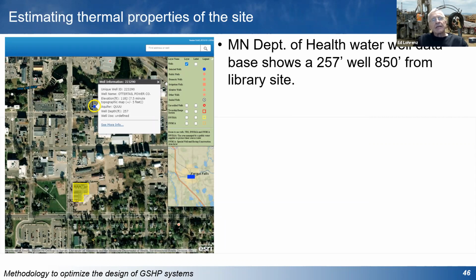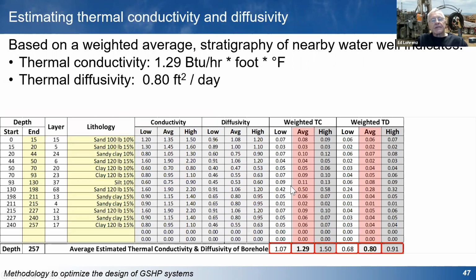First of all, in addition to the energy loads that we're trying to deal with, we've got to try and figure out what the geology is, what that can handle. Minnesota has a very good water well database. Here's where the library was; about 850 feet away from the library, there was a well that was drilled to a depth of about 257 feet. We got the stratigraphy. We could estimate what the thermal conductivity was. Basically, we based the initial size of the ground heat exchanger on a thermal conductivity of 1.29 BTUs per hour per foot per degree Fahrenheit, about the average of what you would see based on the stratigraphy that we found in that water well.